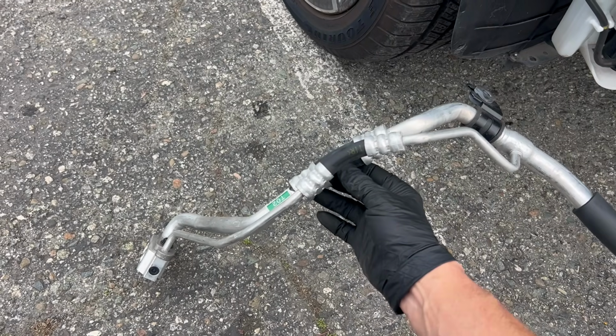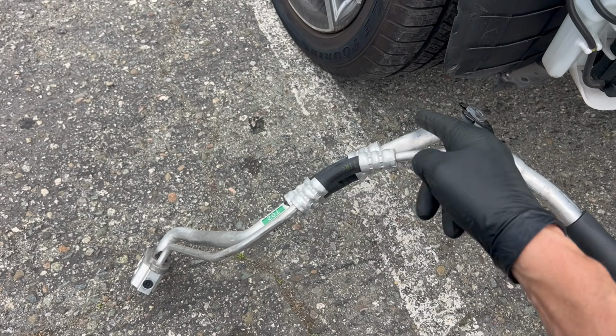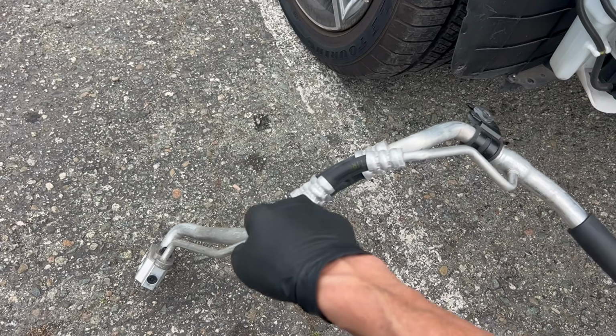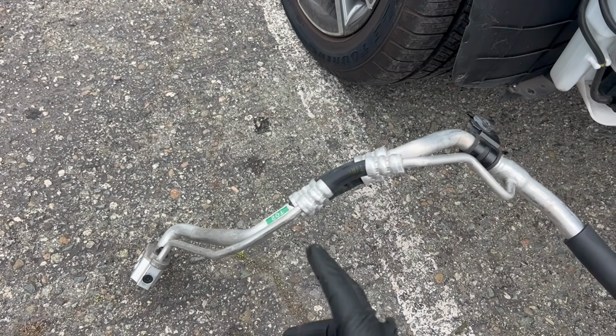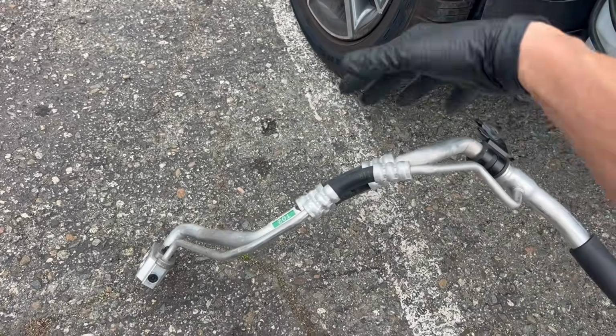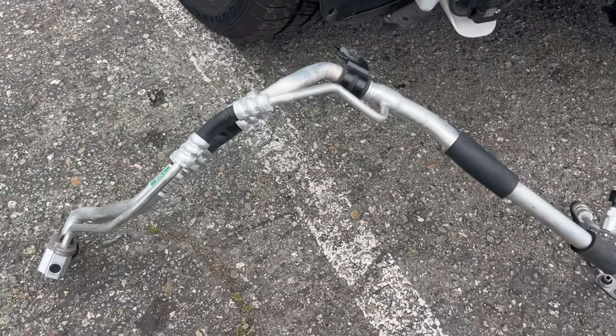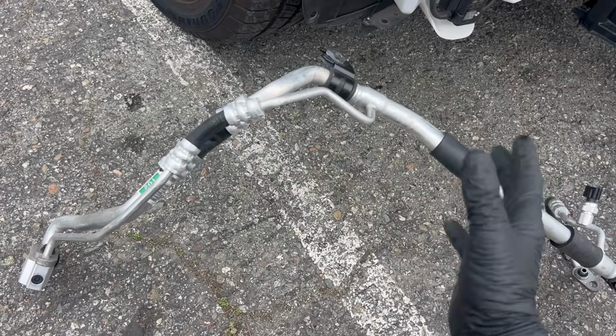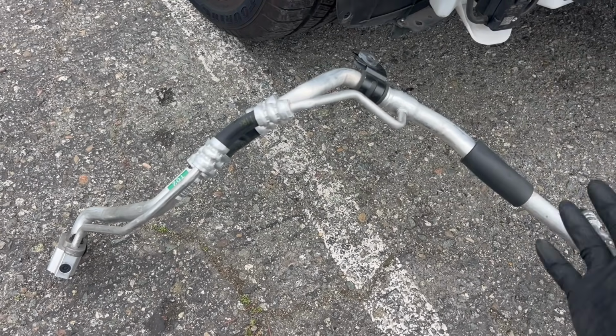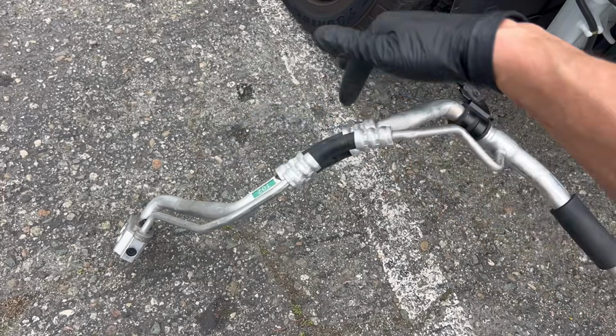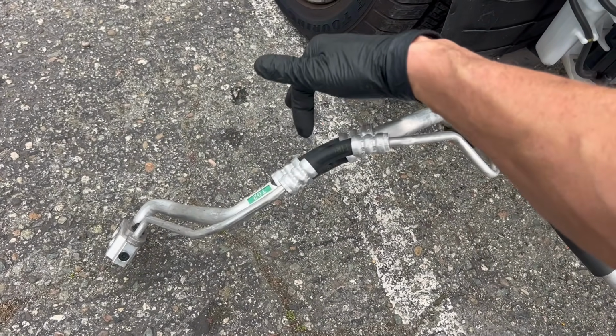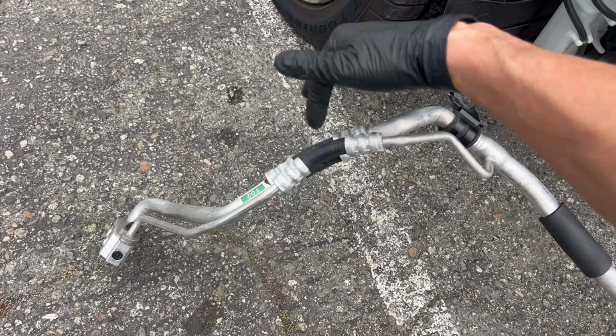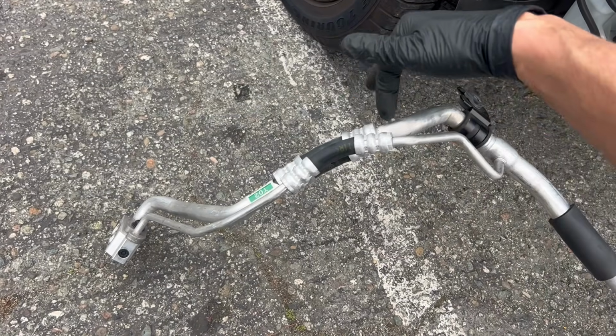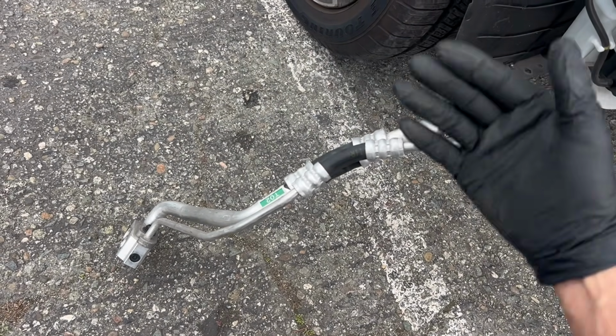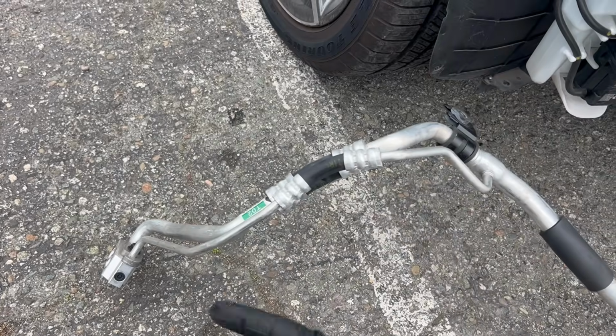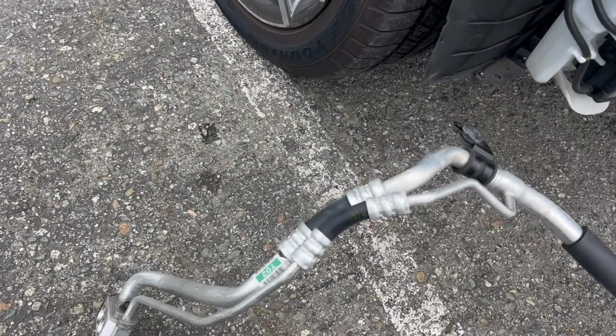I had an inner line suction line by a compressor collapsed, and there was no temperature drop across the hose because it was 100% collapse. And there is so much radiant heat given off by the exhaust manifold right here, and then the blowing across the radiator had 160 or 70 degree air blowing across both the metal. Since there was no refrigerant flow, both sides of the metal were at equal temperature, but it was collapsed into the hose. And somebody would say, oh, you measured a temperature drop.